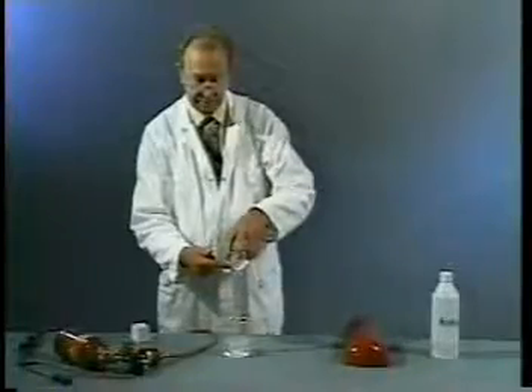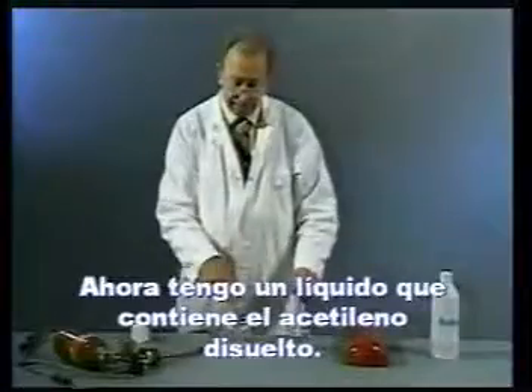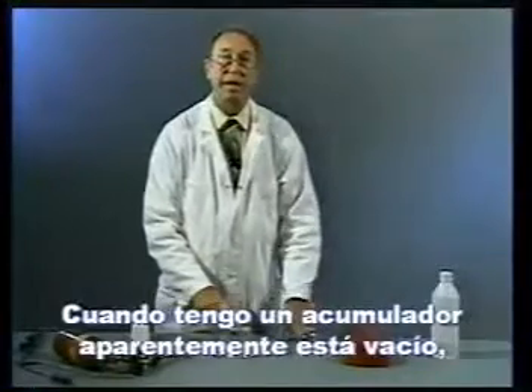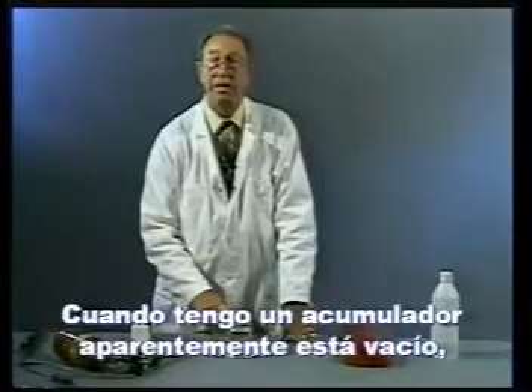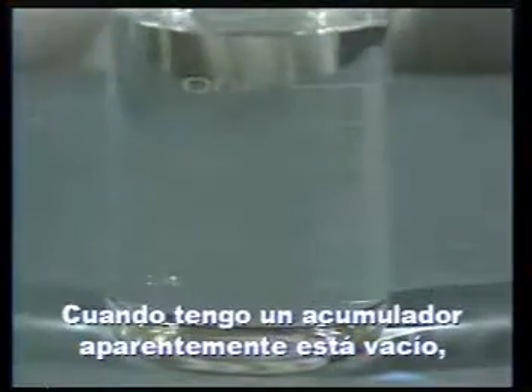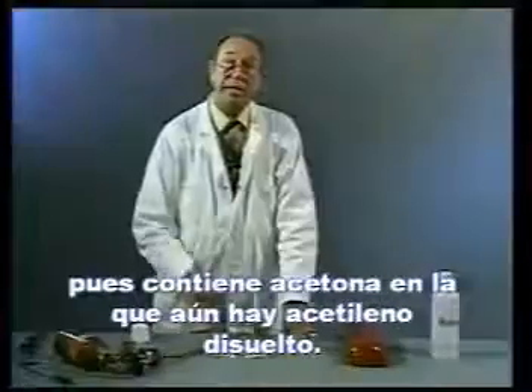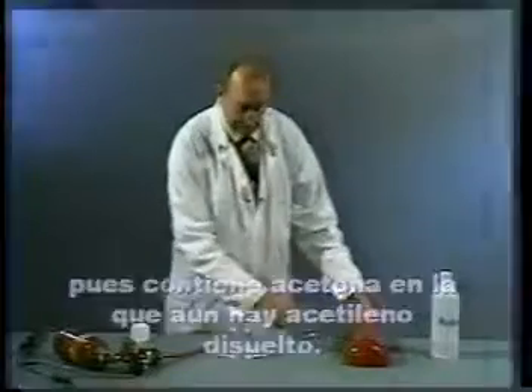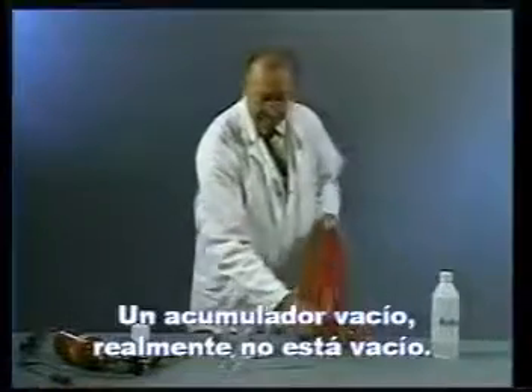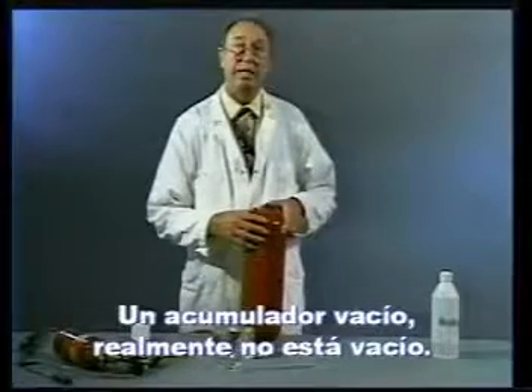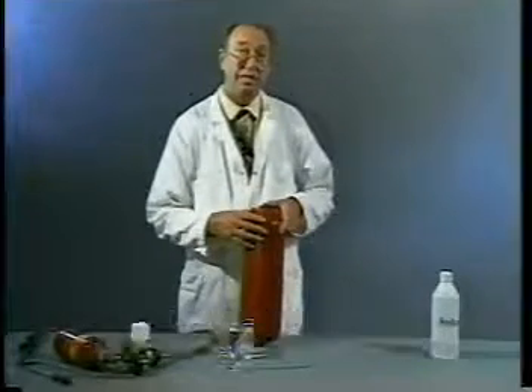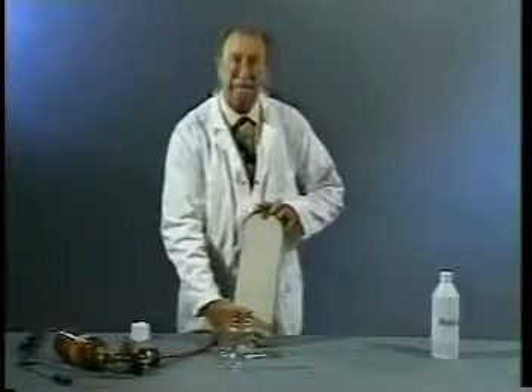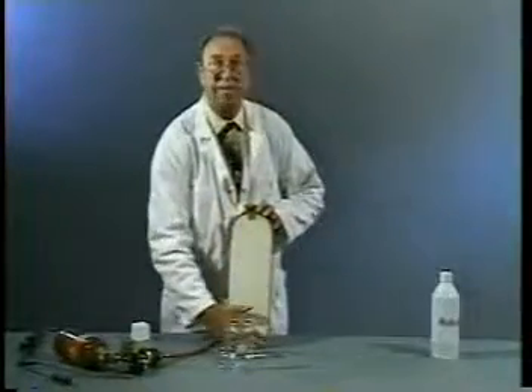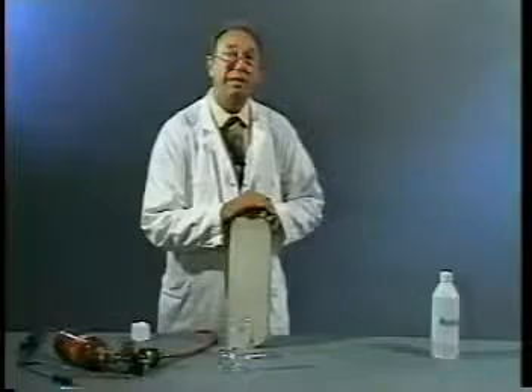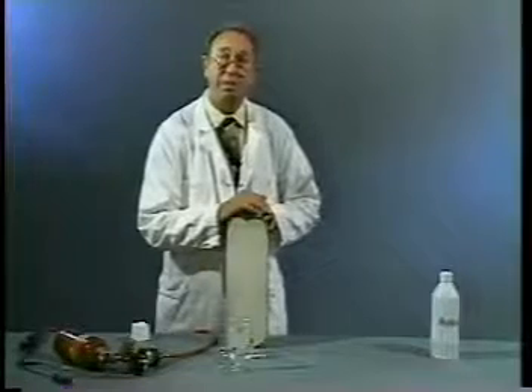Now we are emptying the flask again. And now I can ask you, is this still the same acetone as it was before? No, it's not. This acetone contains acetylene gas. And this means also that when I have such a cylinder and it's empty, it is not empty, because you still have the solvent in here very evenly distributed. There is the gas dissolved, so everybody should remember that an empty acetylene cylinder is not to be considered empty.